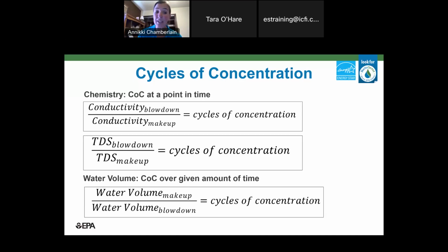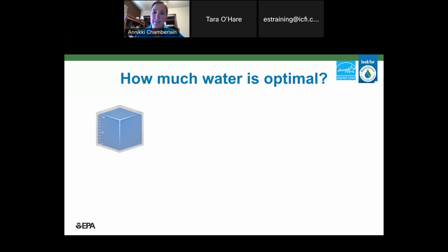What is ideal is using the water volume, the gold star for calculating cycles of concentration. Basically, we're going to look at the volume of water coming in divided by the volume of water leaving, and that's also going to give us our cycles of concentration. What's nice about that is it's giving us our cycles over a period of time. It could be a day, a week, a month, or a year. And that also accounts for anything that could have happened with sensors and things like that. So if at all possible, and that data is collected through submeters, which we will get to, that is the gold star for measurement.